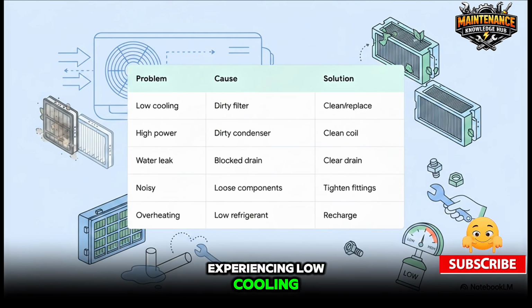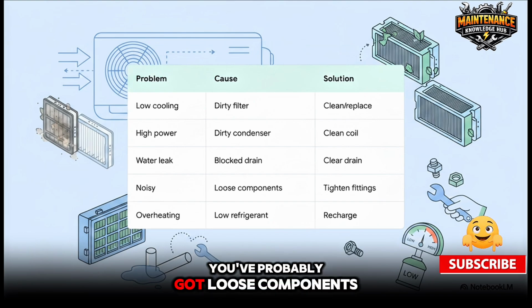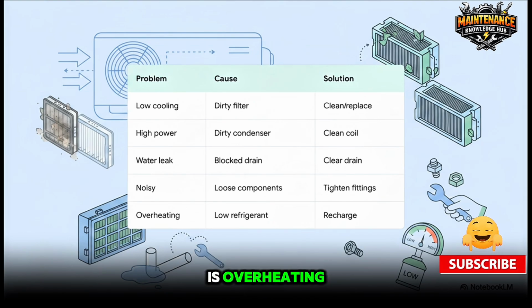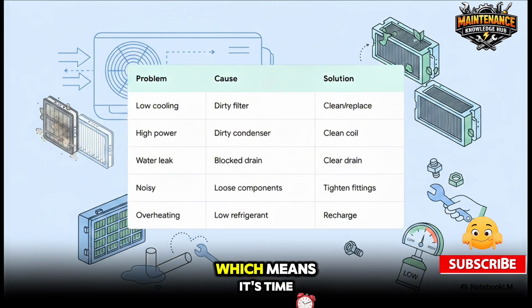Experiencing low cooling? The cause is very likely a dirty filter, so simply clean or replace it. Seeing high power consumption? That's often a dirty condenser coil struggling to release heat, so go ahead and clean the coil. Water leaking everywhere? That usually points to a blocked drain line that just needs to be cleared out. If the system sounds excessively noisy, you've probably got loose components that need their fittings tightened. And if your compressor's overheating, you might be dealing with low refrigerant, which means it's time to call a pro for a recharge.